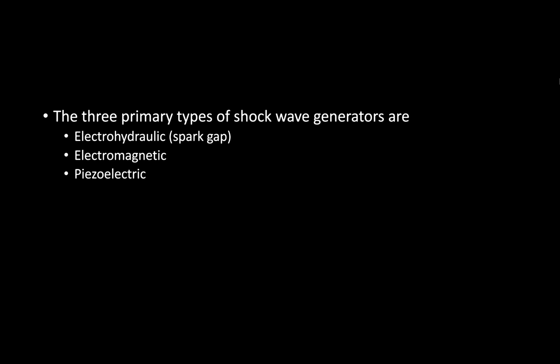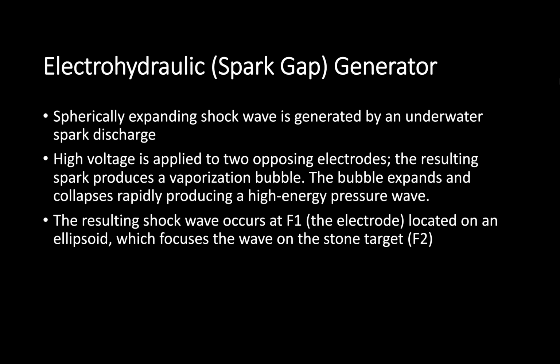Good. So how does this ESWL work? What are all the types of energy sources? There are three types of lithotripsy which have been described: electrohydraulic, piezoelectric, and electromagnetic. The electrohydraulic lithotripsy works through the presence of two electrodes underwater, which have polar opposite voltages. Electrical current is applied to them, producing an underwater spark plug. This vaporizes the water and produces gas bubbles, which then expand and collapse, releasing a shock wave. And the shock wave is then focused onto the stone by means of an acoustic reflector.